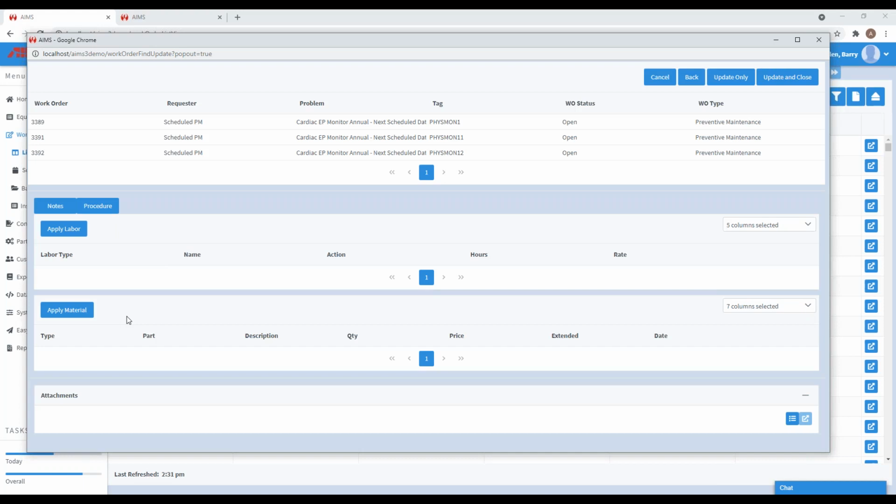You have both of those options from here. So you can both close your work orders. If you're going out and doing 100 infusion pumps, you're going to want to batch close those. You don't want to hit every single work order to put your half hour on it, whatever it takes you to do them. So you can come here, find them all, and close them all at once, or at least close all the passed ones. And then for the failed ones, of course, you should be documenting why they failed and your remediation steps on those work orders. So those might be the one-offs. But for the 99 of the 100 that passed, you can bulk close them in this fashion. Very, very easy to do.